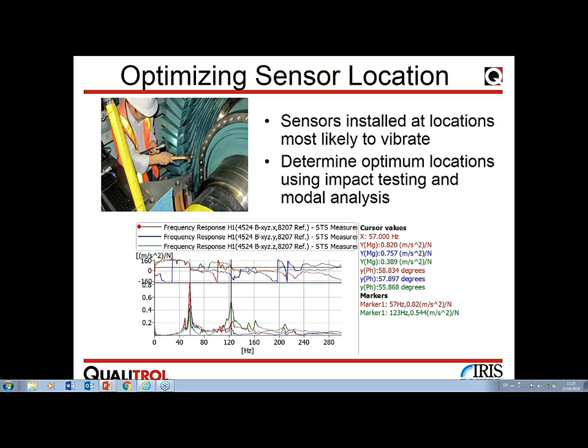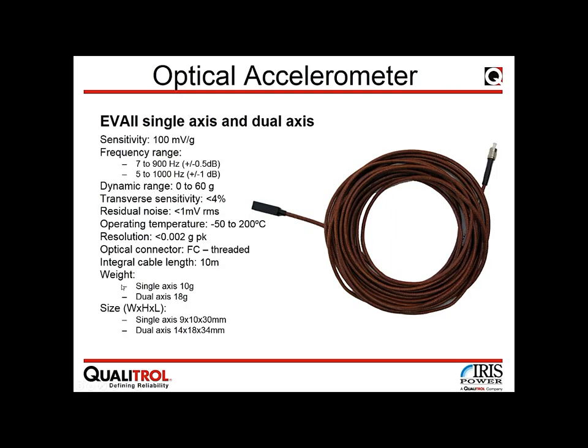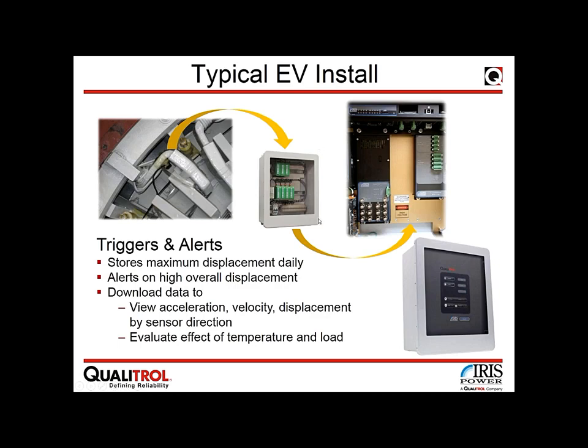The sensor itself is a ceramic, non-conductive accelerometer that covers movement in one or two axes. Information about displacement is collected by integrating the sensor output, providing velocity and displacement of the monitored component. The sensor is non-magnetic, non-electrical, and non-conductive, rated appropriately for temperature and conductivity requirements in the stator end winding. It is connected via fiber optic cable to a converter, which feeds an instrument that provides data analysis and outputs to the operator.